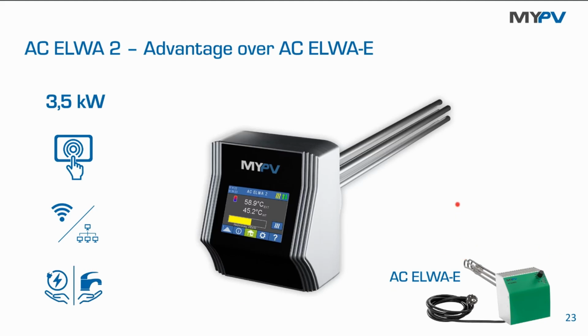For AC ELWA-E and ELWA right now, it's somehow a problem in some cases that the plumber and the electrician work together on one device. That's why we decided to separate the AC ELWA-2 when it comes into the box, into 2 parts: the immersion heater, the heating rod, separated from the control unit. This means the plumber can assemble the immersion heater in the tank, check the sealing, and refill the tank. Later on, the electrician comes, sets on the power stage of MyPV, and connects it with the signal source. This can be a scenario, and it's definitely much more attractive than the AC ELWA-E to install.